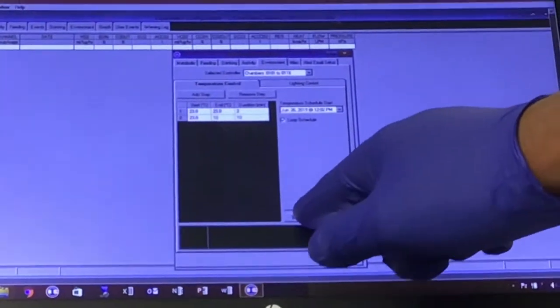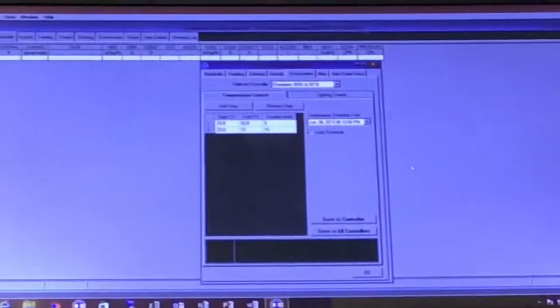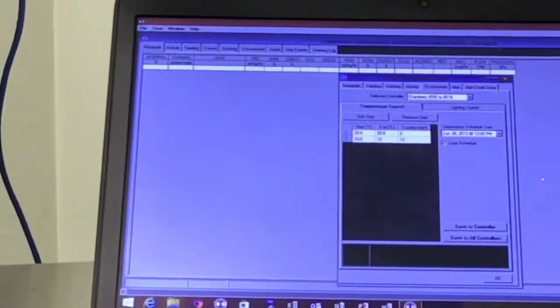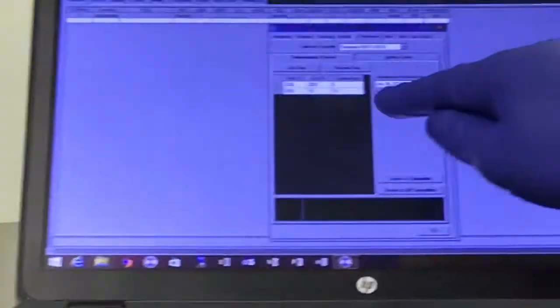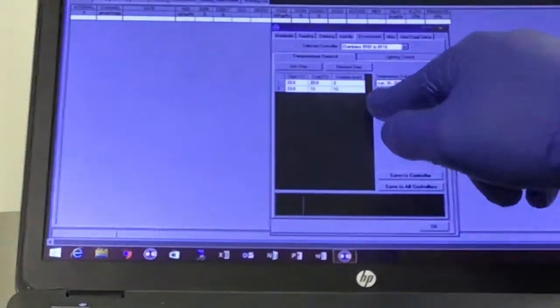Remember to always save it to the controller. If you add it and you don't save it, the command is never sent. So normally, just adjust it to 23 degrees? Yeah, if you just want 23, you put start 23 and 23 forever. And look, you can even put 1 minute, 720, 1440 minutes, which is a day. And look, this is the guy that's going day after day after day. You do 1 day, 22, 22, look, you do it forever.